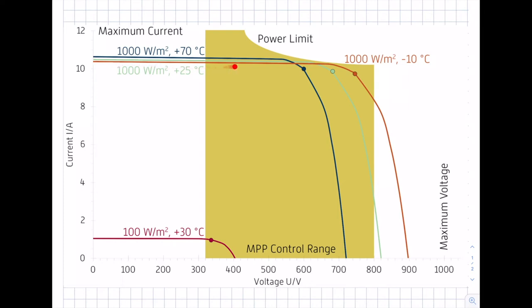The orange curve represents a clear sky day in winter: 1000 watts per square meter at noon, but a module temperature of minus 10 degrees Celsius. In this case, smaller module temperatures lead to an increase in voltage, represented by the shift of the orange curve to the right. The MPP point also moves to the right, meaning the maximum power point voltage has increased, but it must still remain within the MPP control range.